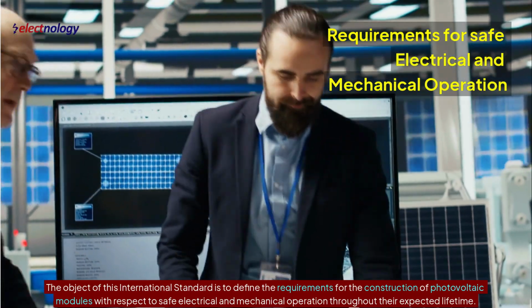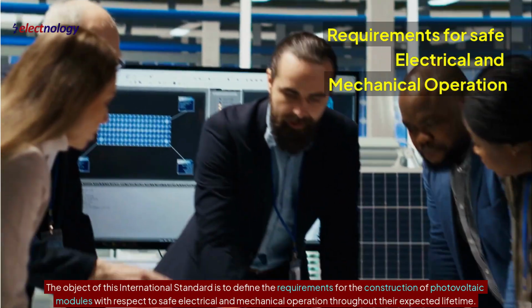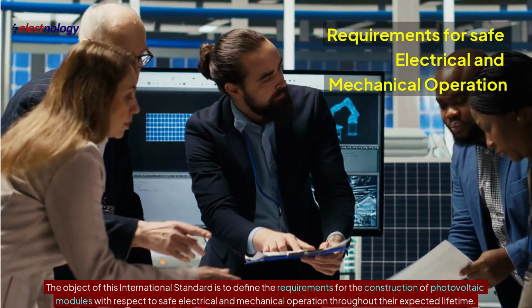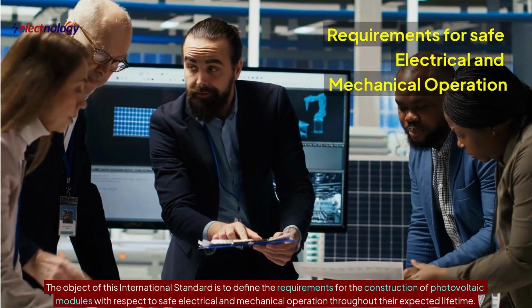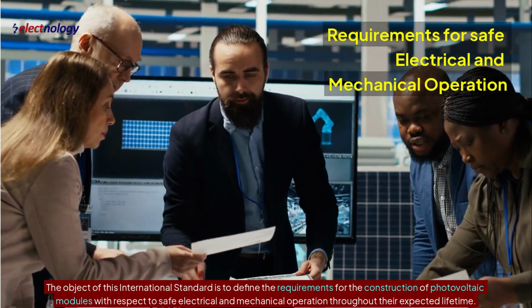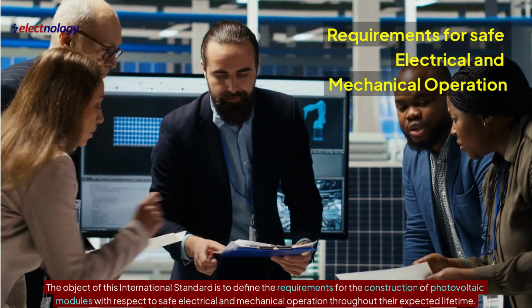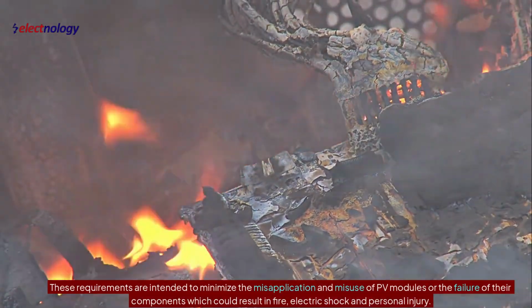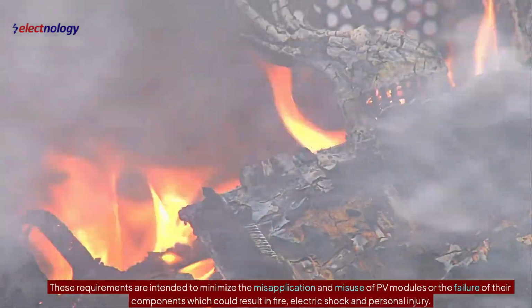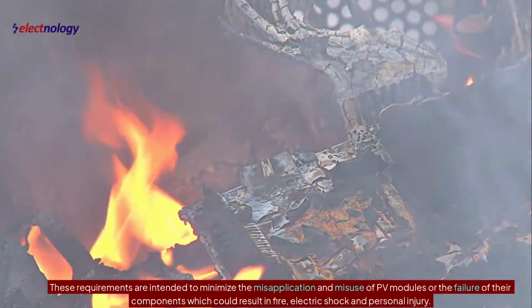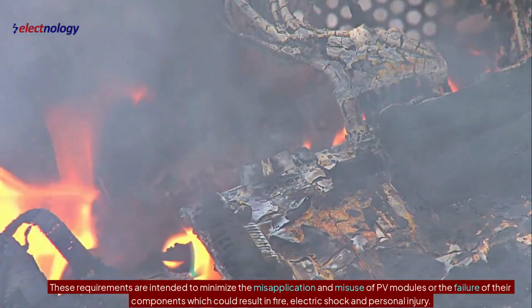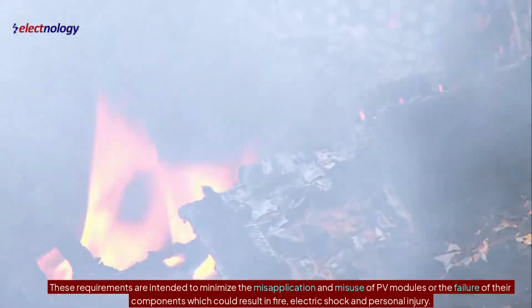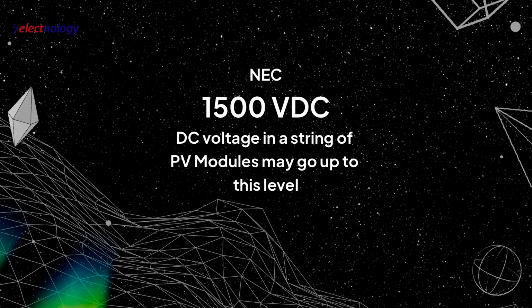The object of this international standard is to define the requirements for the construction of photovoltaic modules with respect to safe electrical and mechanical operation throughout their expected lifetime. These requirements are intended to minimize the misapplication and misuse of PV modules or the failure of their components, which could result in fire, electric shock, and personal injury. At a commercial solar PV plant, DC voltage in a string of PV modules may go up to 1500 VDC in accordance with NEC.